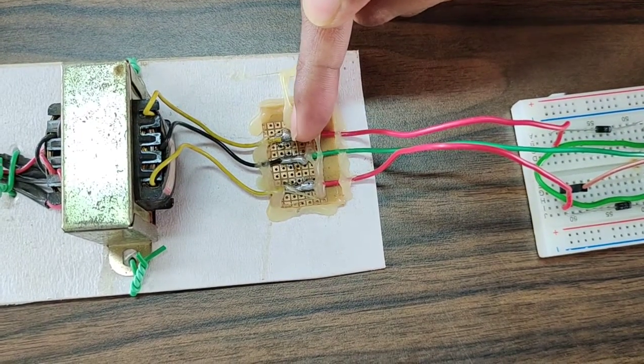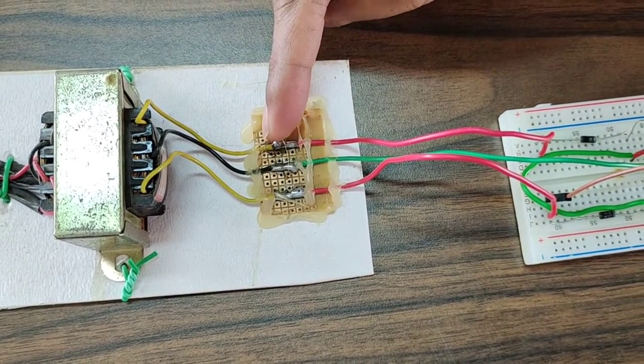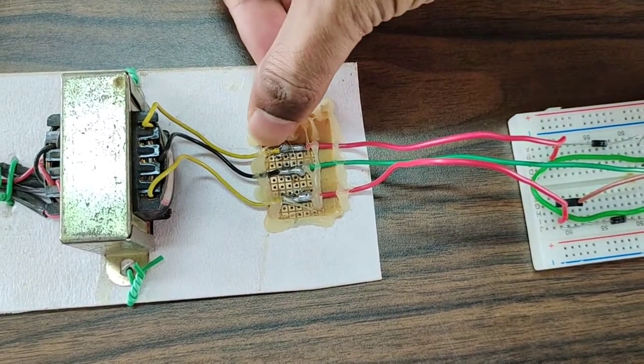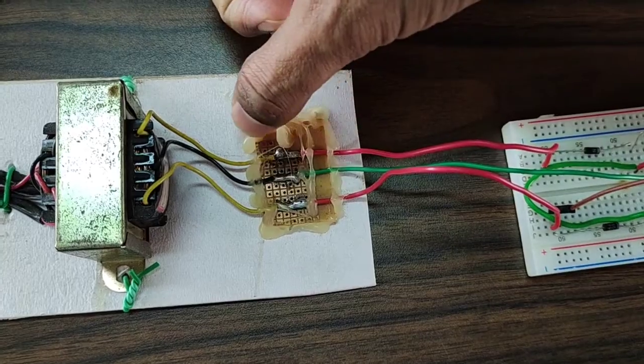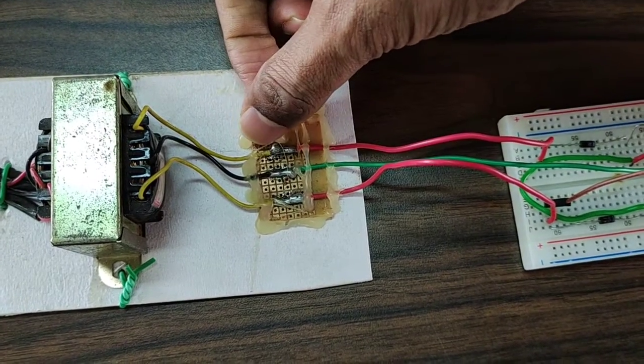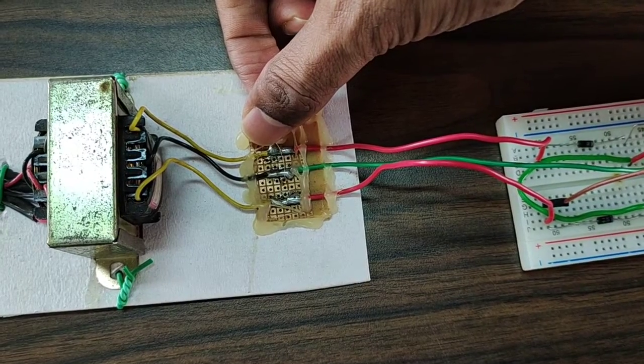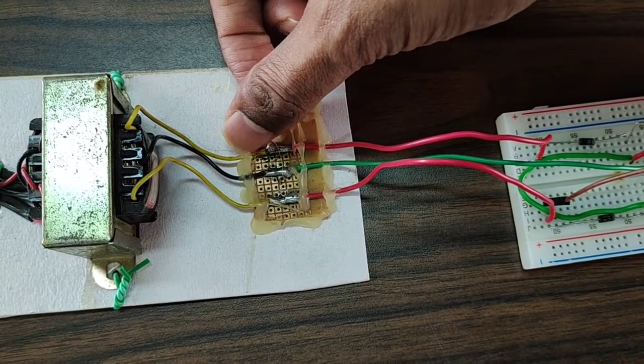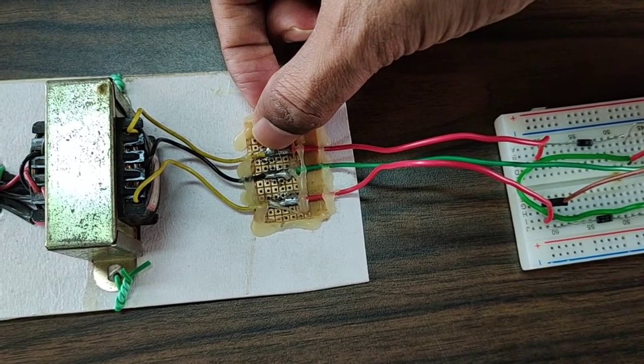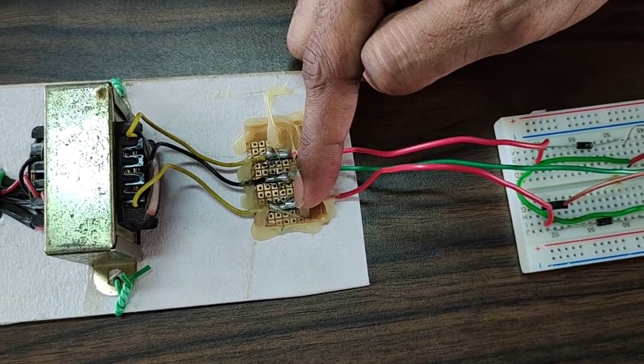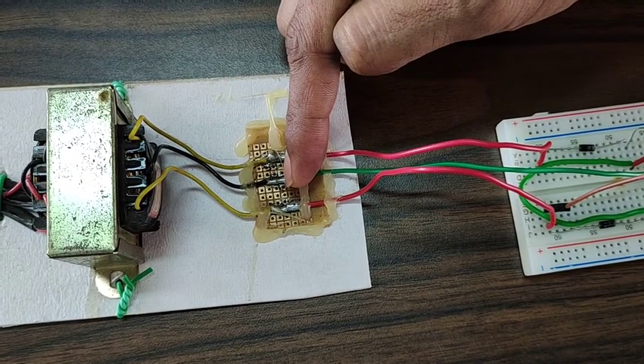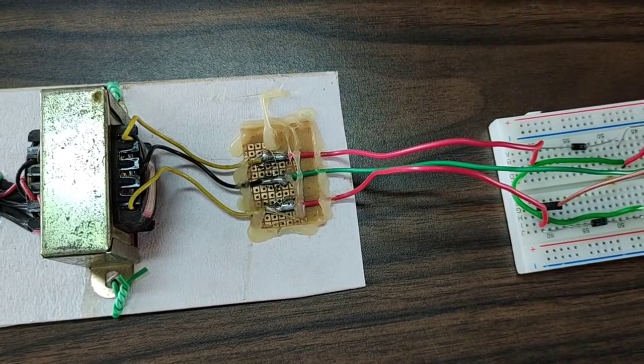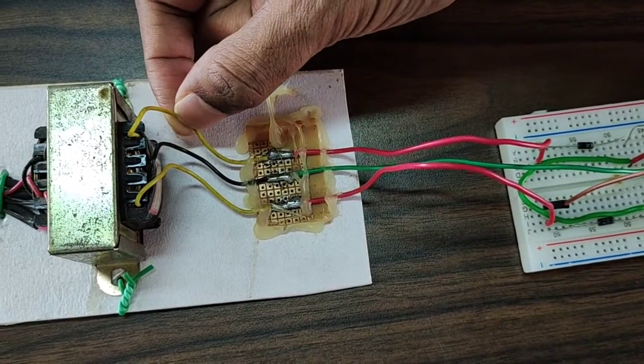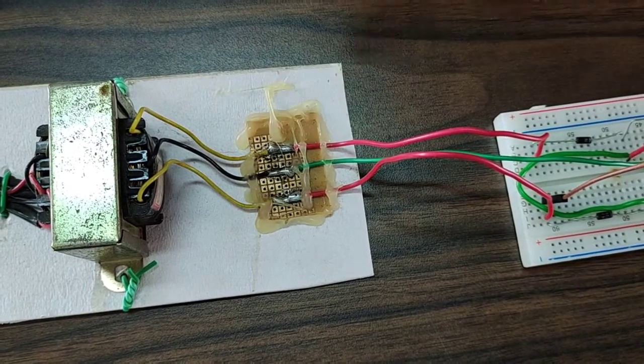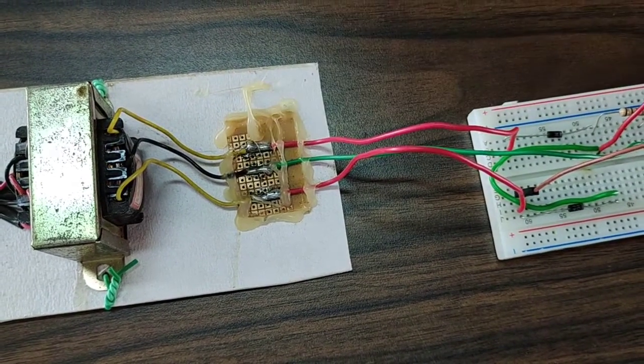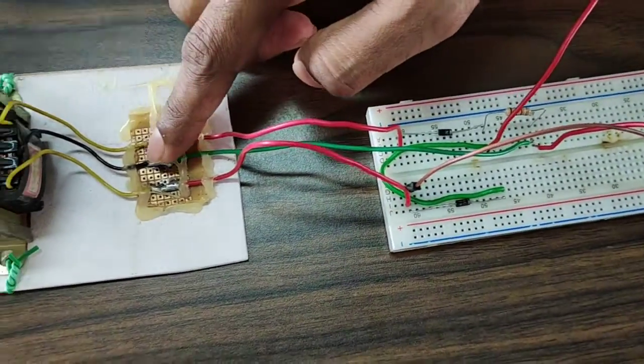Here you can observe that there are three wires. These three wires stand for phase, neutral and phase. So there are two phase terminals. This phase terminal is rated at 12 volt. So the voltage between this yellow wire and this black wire is 12 volt. Similarly, the voltage between the bottom yellow wire and the middle black wire is 12 volt. If you want 24 volts, then you have to connect the first yellow wire and the second yellow wire. So between the two yellow wires you will have 24 volts of supply. Between yellow wire and black wire, 12 volts.